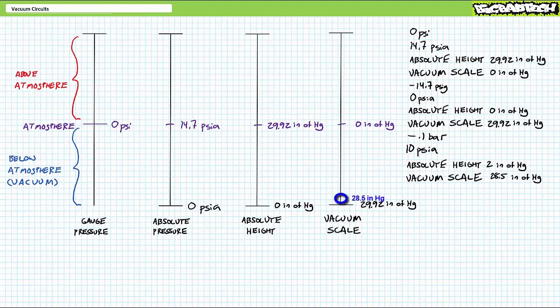Lastly, 28.5 inches of mercury in the vacuum scale means 28.5 inches of mercury got sucked out of the 30-inch tube, leaving roughly only 1.5 inches. Thus, it's an even stronger vacuum than 28 inches, but yet not as strong as a perfect vacuum.